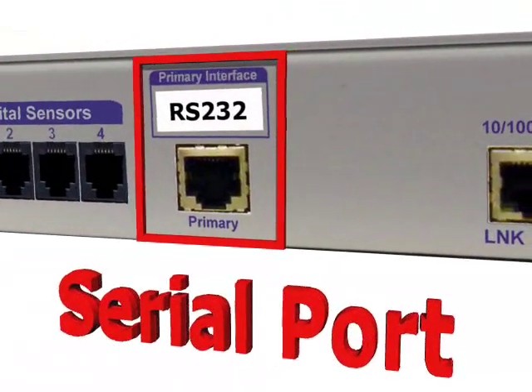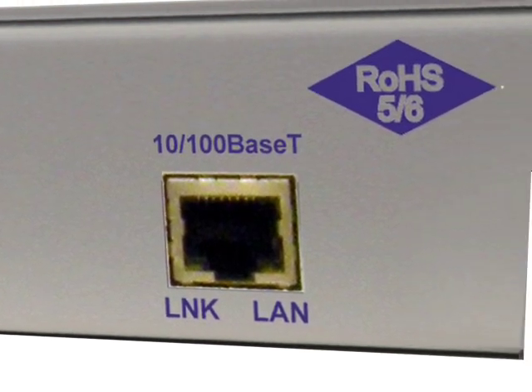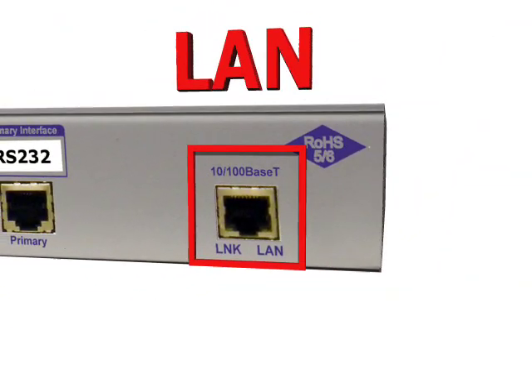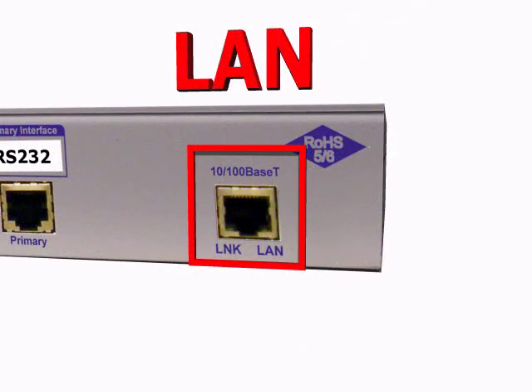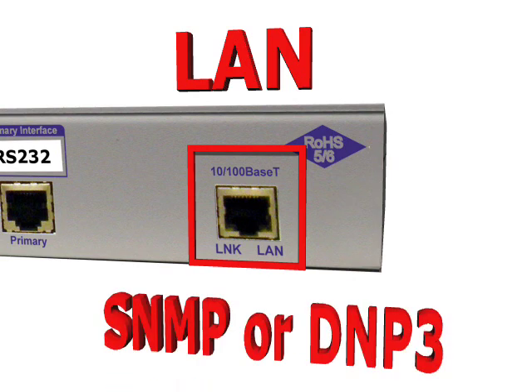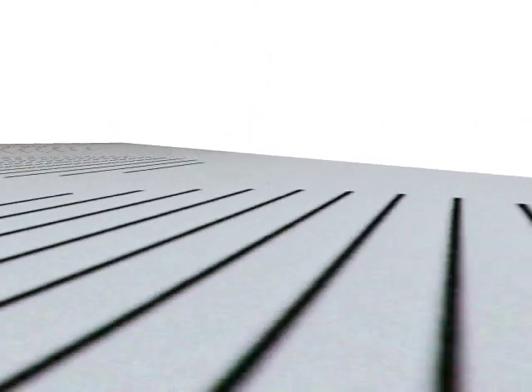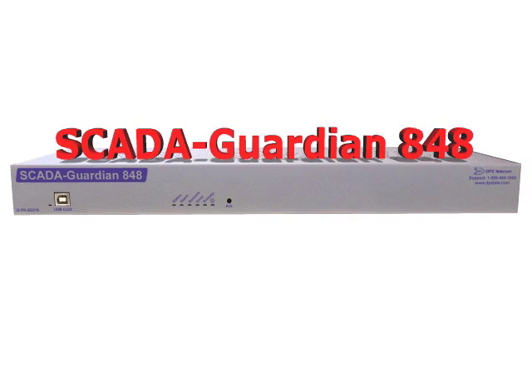One of the biggest factors that differentiates SCADA from other fields that involve remote monitoring is the set of industry standard protocols that are commonly used. While in telecom circles SNMP is more common, DNP3 is really one of the most common protocols in SCADA. That's why you can order your SCADA-Guardian with either SNMP or DNP3 alarm reporting, depending on the system you need to integrate with. Everything that DPS has learned about reliability and ease of installation has been put into the SCADA-Guardian.